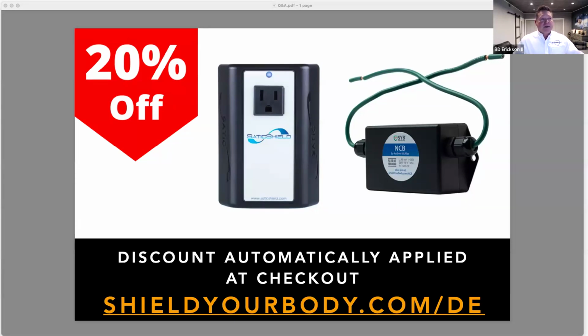Oftentimes they're fine. What we're really doing with ground is making sure someone doesn't get shocked. That's really why you have it. We don't want ground to carry any current. We've talked about that at great length, but there's a chance, if you drop the blow dryer in the tub, that you want the GFCI to trip. Some of the GFIs are actually smart, and then you wouldn't want to use the Satic with it because you wouldn't want to interrupt that signal.